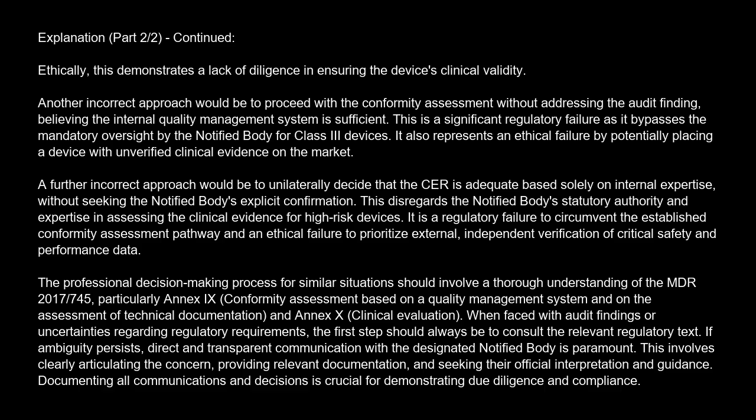Another incorrect approach would be to proceed with the conformity assessment without addressing the audit finding, believing the internal quality management system is sufficient. This is a significant regulatory failure, as it bypasses the mandatory oversight by the notified body for Class III devices. It also represents an ethical failure by potentially placing a device with unverified clinical evidence on the market.